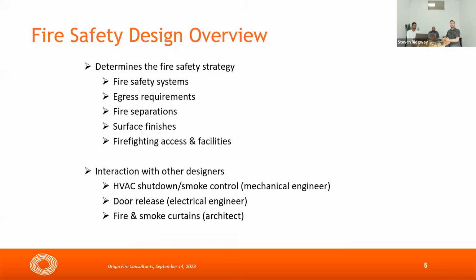We also have some interaction with the other designers. As the fire safety engineer, we'll give a requirement. We won't go too much into detail. And we'll say things like, you might require the ventilation system to shut down on the fire alarm, to stop smoke spread throughout the building. You might actually use the ventilation system to control spread of smoke, in which case you might say, pressurize this zone, extract from that zone. You'd also have things like your door release, where you say on fire alarm, open these doors so that people can get out safely. And then the good fun one of fire and smoke curtains, which obviously you'll talk to your architect about.